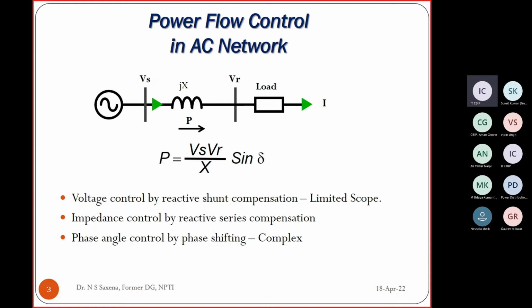You cannot change much. Then the second thing is impedance control, which is inversely proportional to impedance X. In a transmission line, it consists of towers and conductors. You can calculate the impedance using GMD, GMR, and all that, but you cannot change that by normal means - it is fixed. So impedance also cannot be changed.